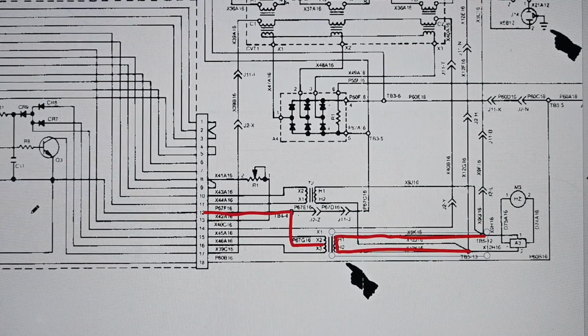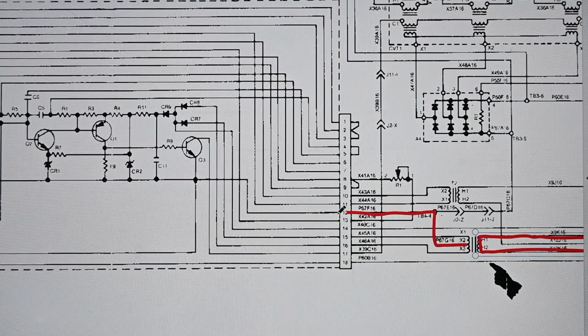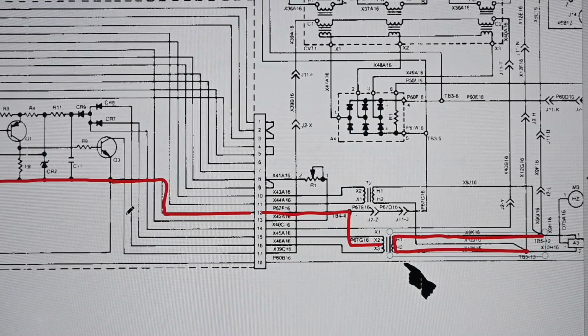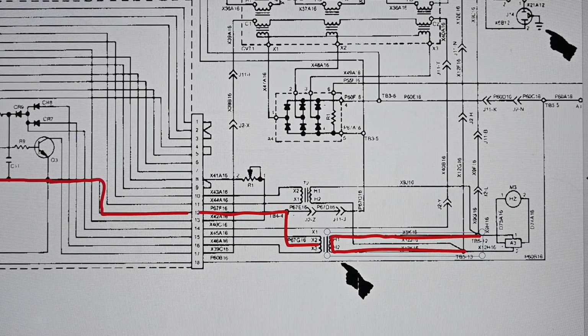If we look at terminal 12, move this over a little, you can see what happens. This comes over, goes all the way up here. This is basically a ground connection, or common, across many components in the regulator, but it's not ground as in the generator set ground. There is no ground connection, it's important to know that. But it is a common circuit point within the regulator.